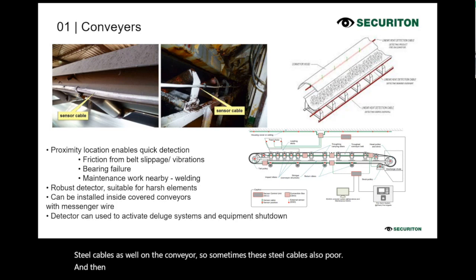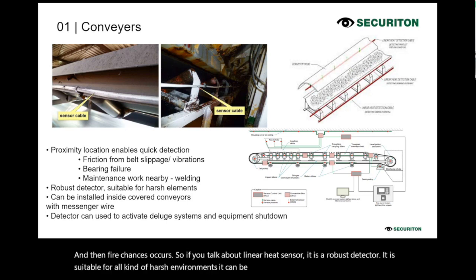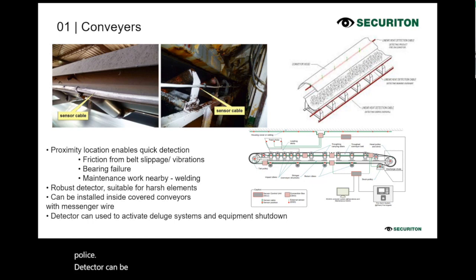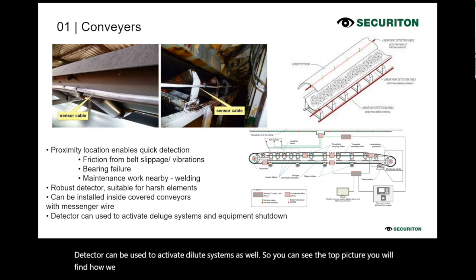The sensor is a robust detector. It is suitable for all kinds of harsh environments. It can be installed inside covered conveyors or on the pulleys. The detector can be used to activate deluge systems as well. So you can see in the top picture how we install our linear heat sensor on or down the conveyor belts.